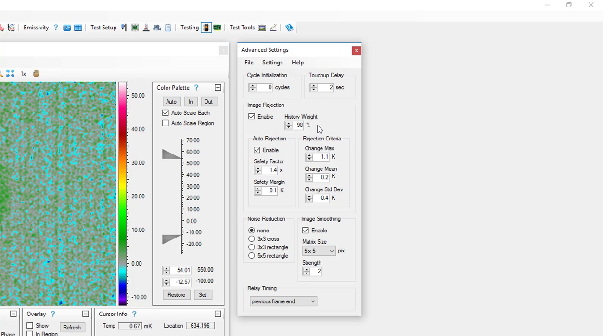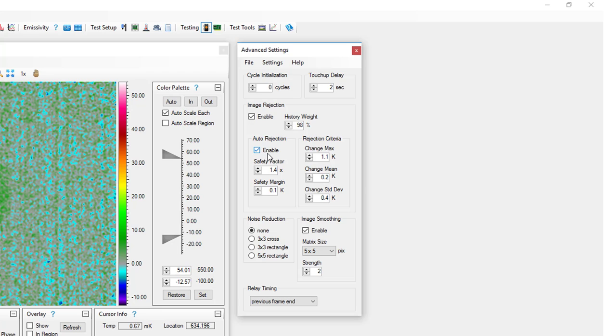History weight determines how far back in the past previously captured images are used for the comparison. A good starting point for this value is 98%. For the majority of lock-in tests, image rejection should be enabled and auto-rejection should be enabled.